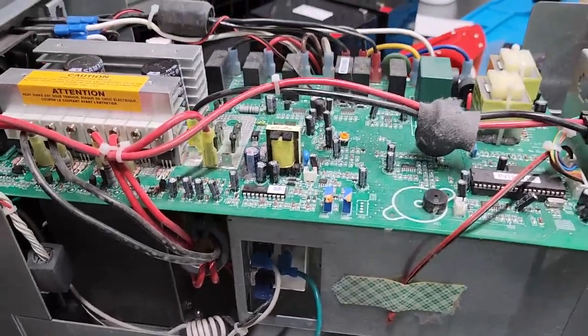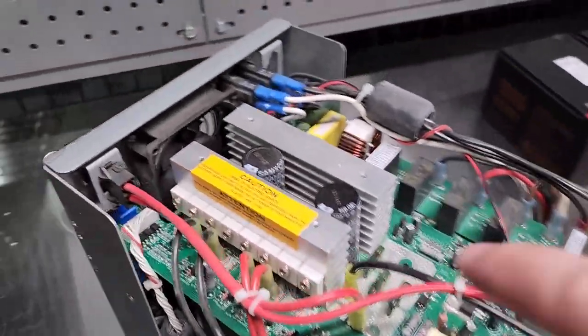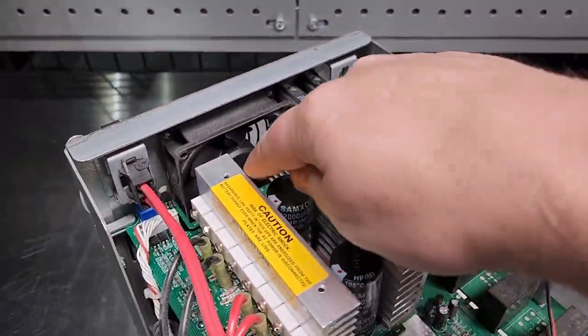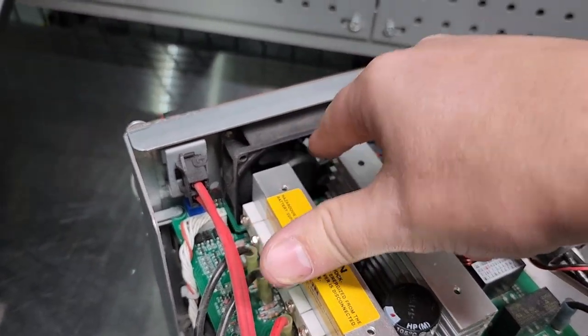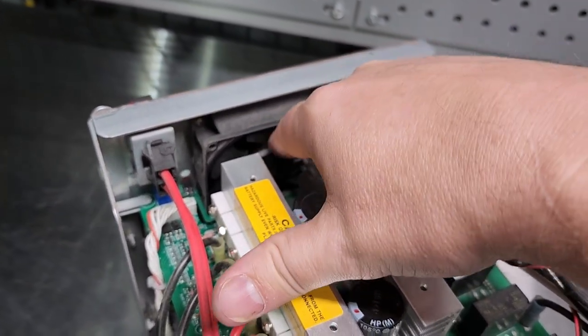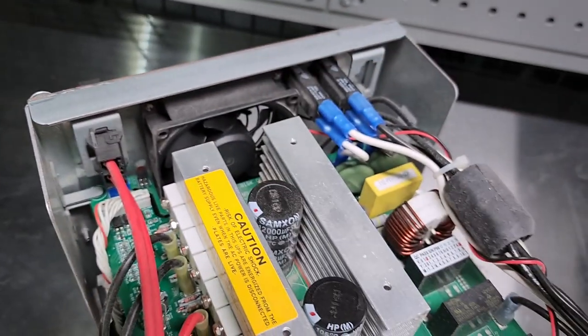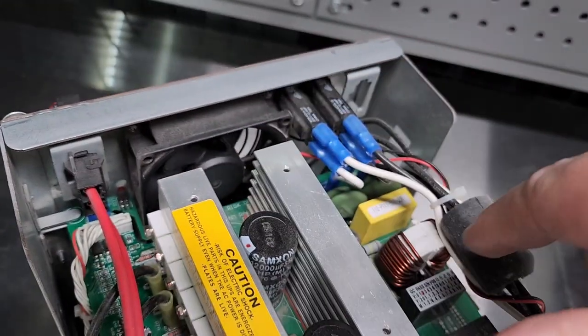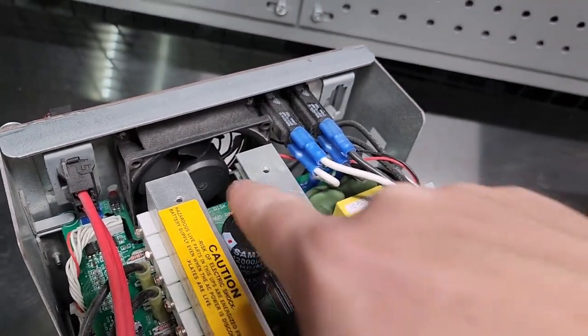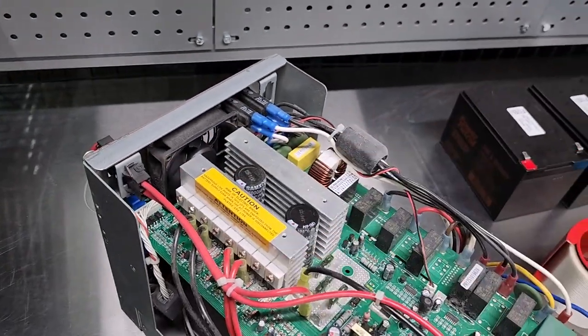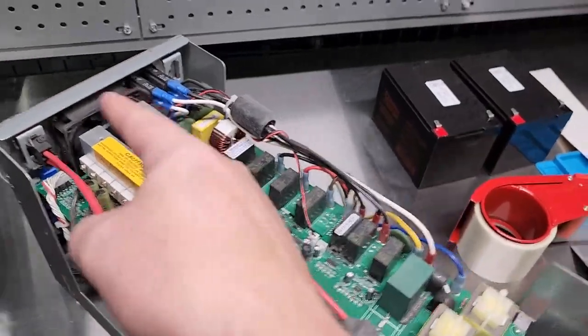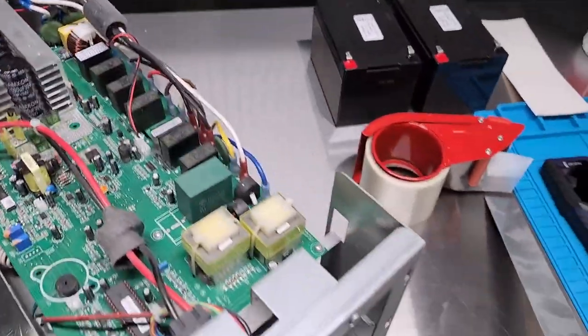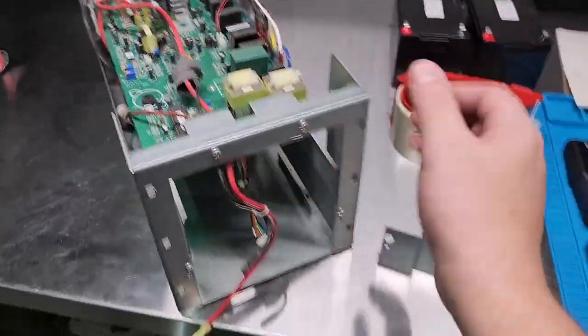That is a pretty good run-through of a UPS system. Probably the last thing you really want to check, this fan. Make sure that it spins nice and freely. You can see, I spin it with my finger and let it go. That's a good sign. As soon as I take my finger away, if it stops immediately, that fan needs to be replaced.